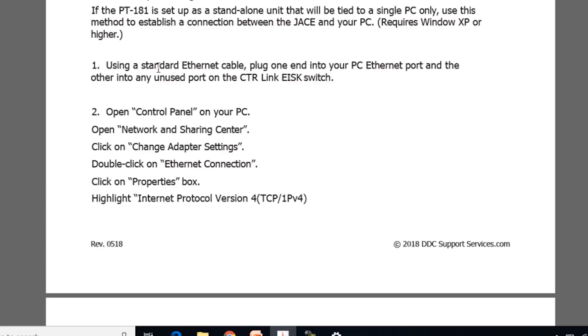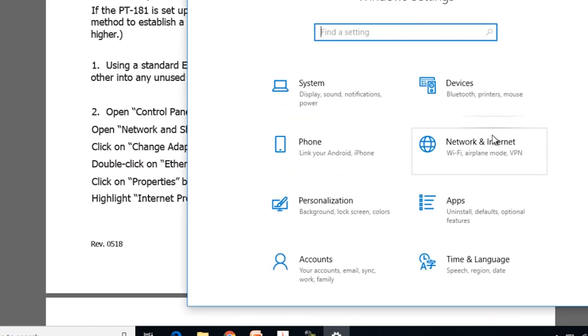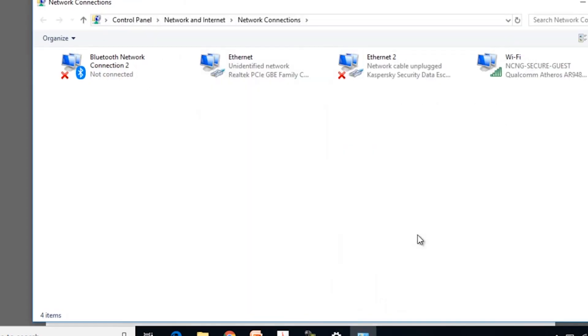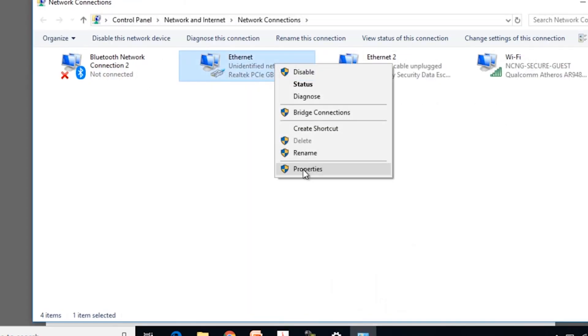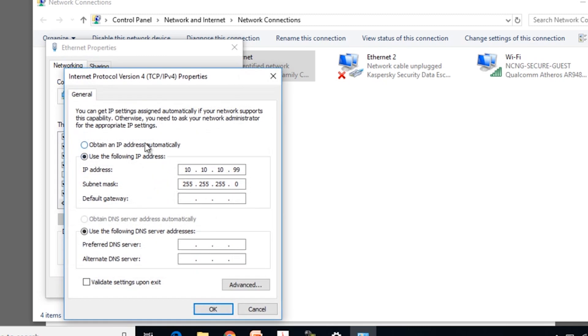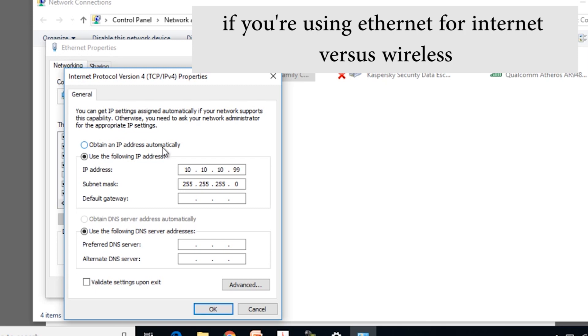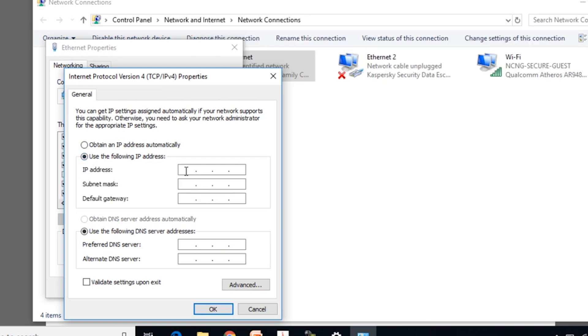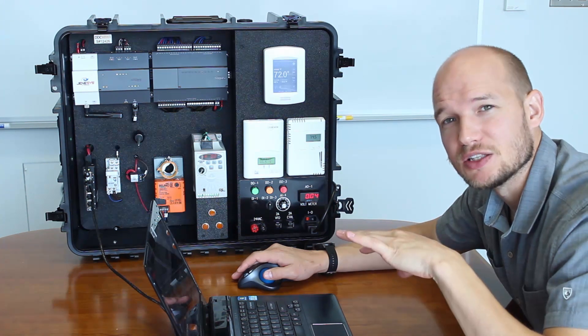Here in step two, we open the Control Panel and change some network adapter settings. Go to Network, Change Adapter Options, select the Ethernet port, go to Properties, find IPv4 Properties. If you're on the internet you'd be obtaining an IP address automatically, but since we're trying to get into the JACE, we're going to enter an IP address of 10.10.10.99 with a subnet of 255.255.255.0, click OK and save.